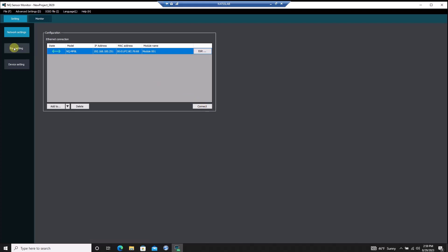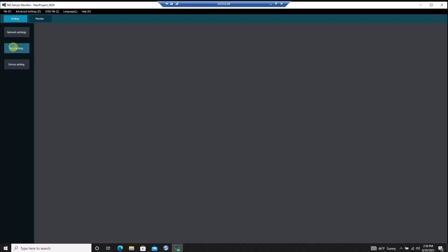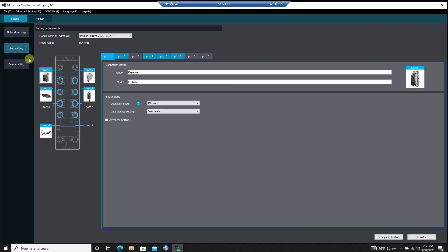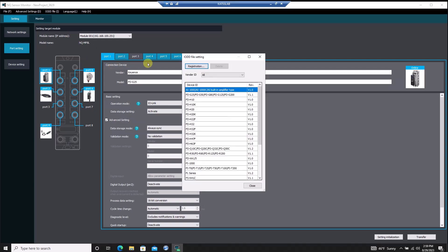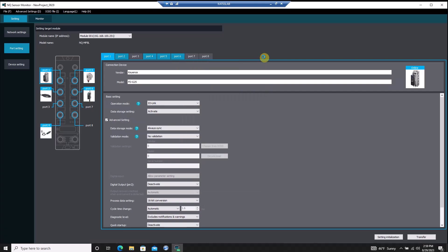In the Port Settings menu, I can configure the operation that each port is performing, along with some extra functions like data storage modes that back up IO-Link sensor data, and sensor validation settings for each port. Any Keyence IO-Link devices will automatically appear when connected to the NQ, but any third-party IO-Link sensors can be added by uploading the IODD file of that sensor to the software.